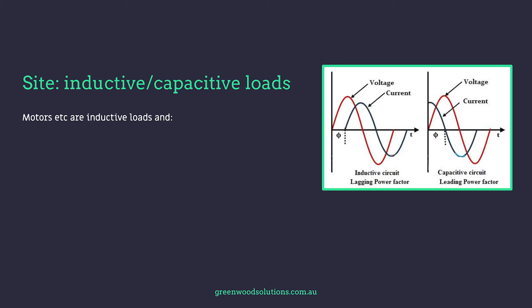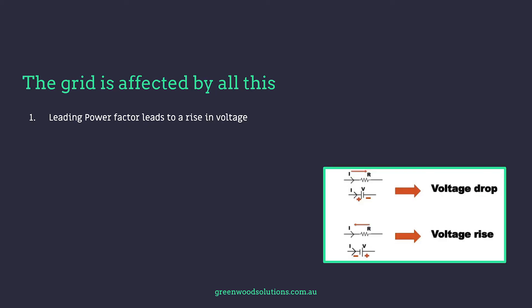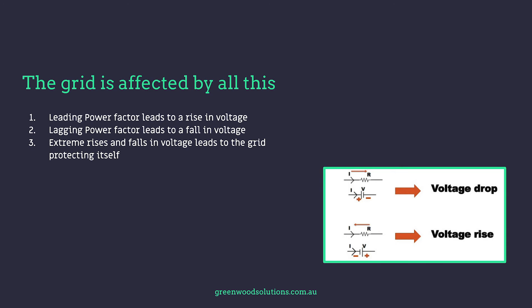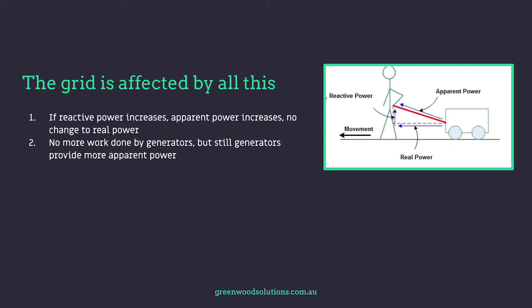On the site, if we have inductive and capacitive loads — motors etc. are inductive loads — the current lags the voltage, giving a lagging power factor. If capacitive loads, the current leads the voltage, hence a leading power factor. The grid is affected by all this: a leading power factor leads to a rise in voltage; a lagging power factor leads to a fall in voltage. Extreme rises and falls in voltage lead to the grid protecting itself. If reactive power increases, the apparent power increases as well, but there's no actual change in real power — no more work done by the generators, but still generators provide more apparent power.